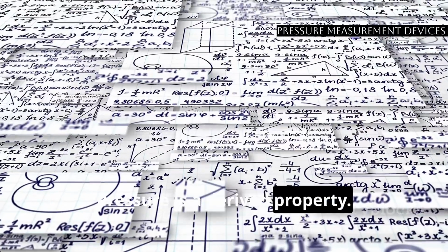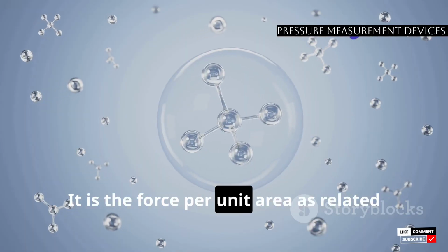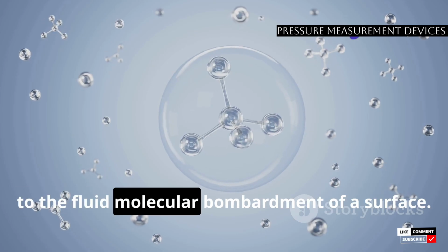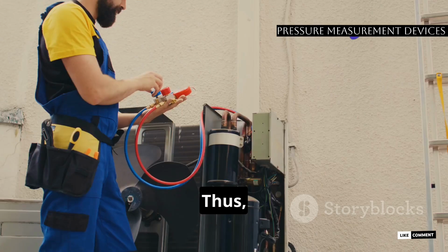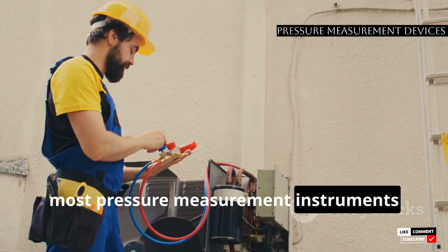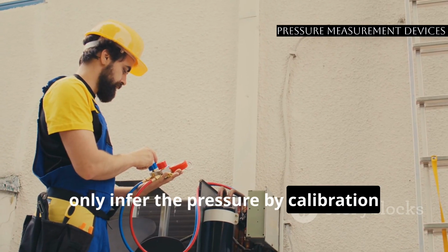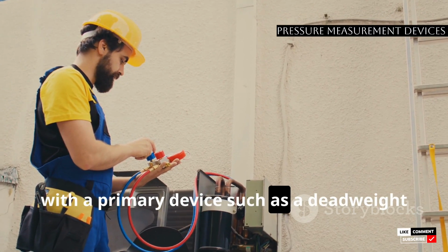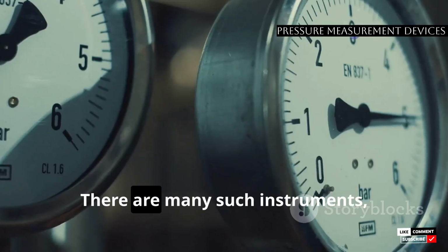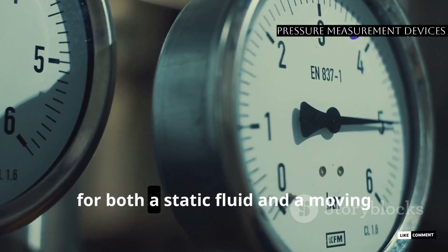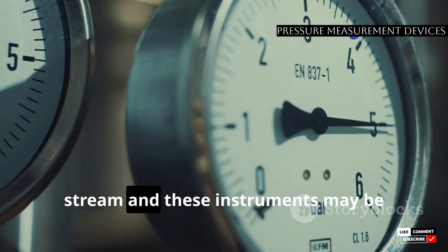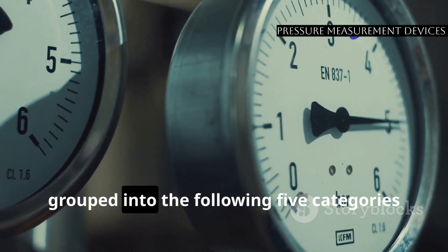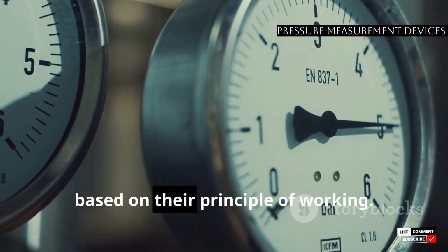Pressure is a derived property. It is the force per unit area as related to the fluid molecular bombardment of a surface. Thus, most pressure measurement instruments only infer the pressure by calibration with a primary device such as a deadweight piston tester. There are many such instruments for both a static fluid and a moving stream, and these instruments may be grouped into the following 5 categories based on their principle of working.